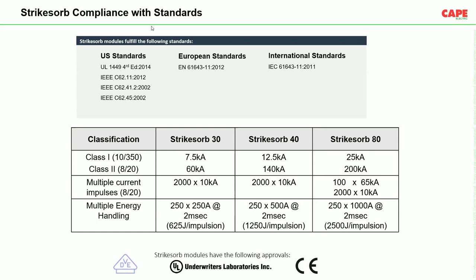Each of the current flow is 250 amps, and that means the surge current is 250 amps, and the duration of the current flow is 2 millisecond. So in comparison to a microsecond phenomenon, the long duration stroke is a few milliseconds. So the last test, multiple energy handling, is for a long duration. Long duration in the sense, in comparison to an 8 by 20 microsecond stroke, 2 millisecond is almost 100 times or more duration.